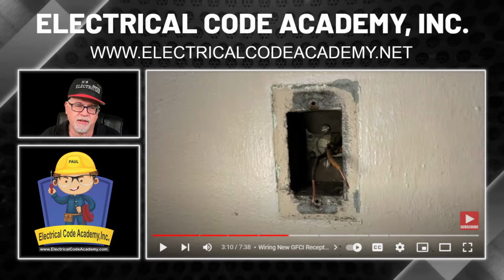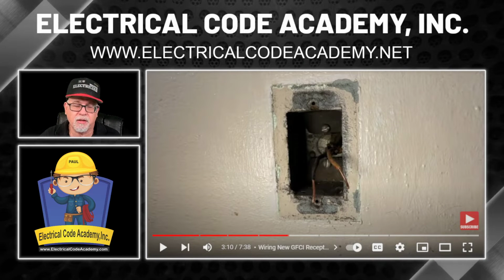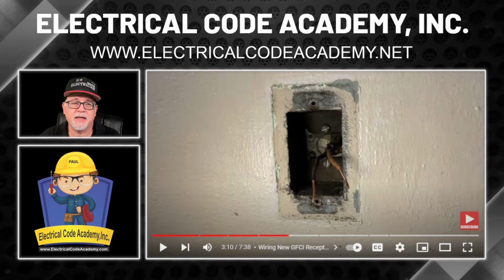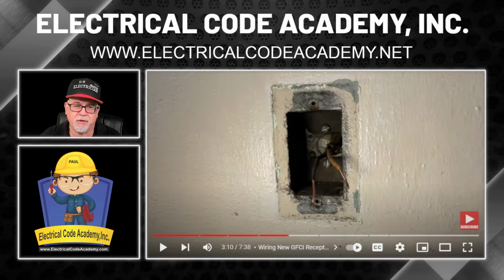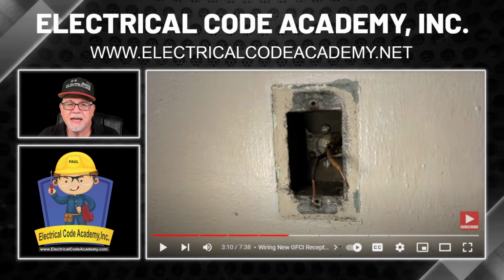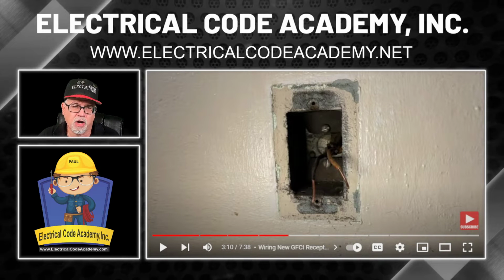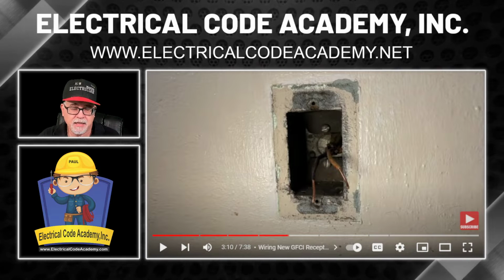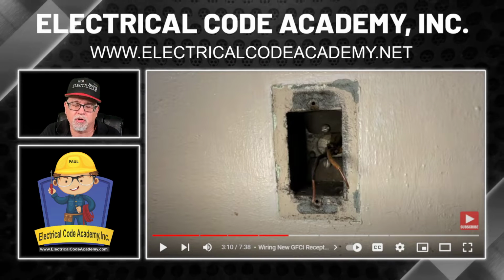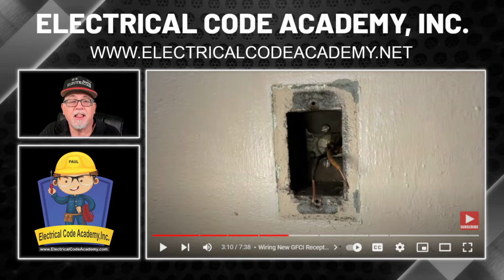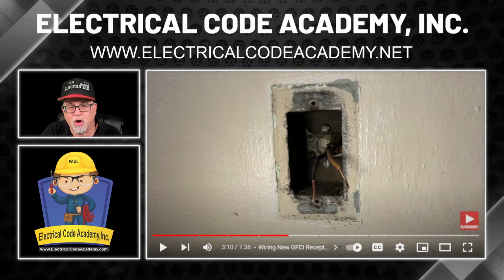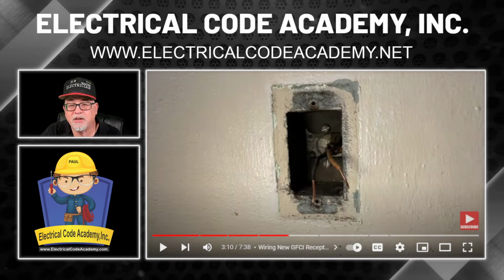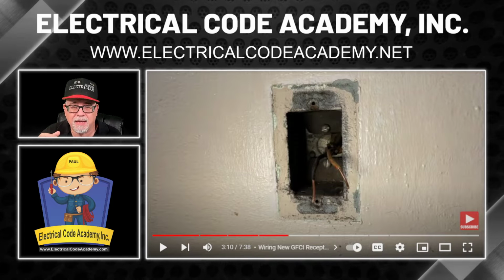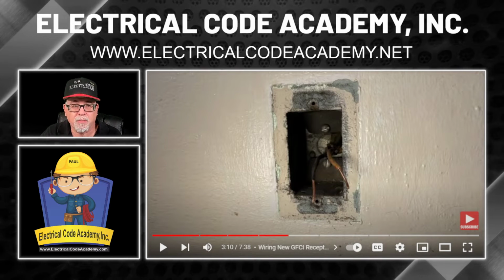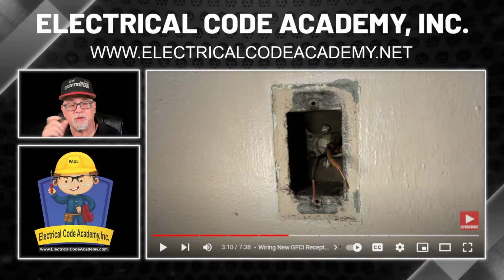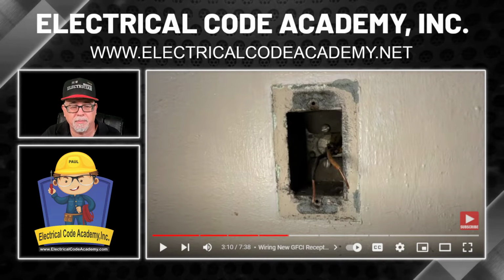Flippers want to do that all the time because, in close proximity to a panel, it might read out as being a connection to ground as it connects to the panel, and then they end up wanting to use it. BX was never intended for the armor to be used as an equipment ground. AC cable, which is under Article 320 of the NEC, is specifically designed to use the armor as an equipment ground. That way you don't have any equipment grounds inside of the cable assembly, okay? Because you're using the armor and you use a special fitting that's listed for use with the AC cable in conjunction with the metal box.